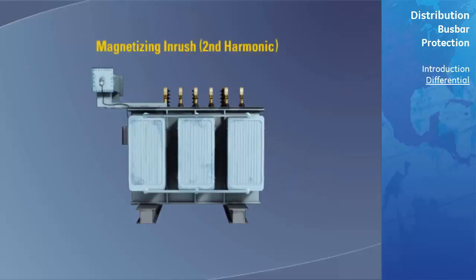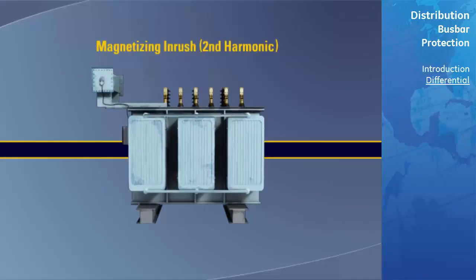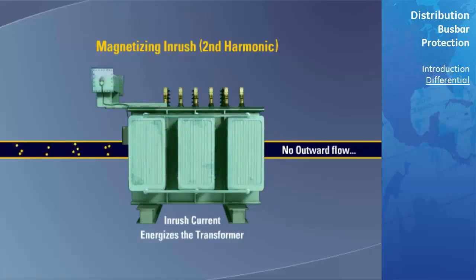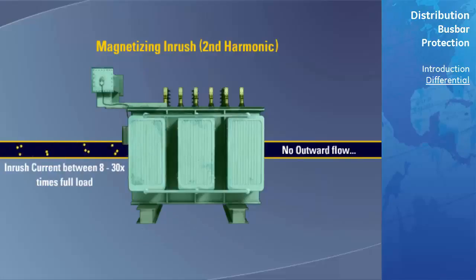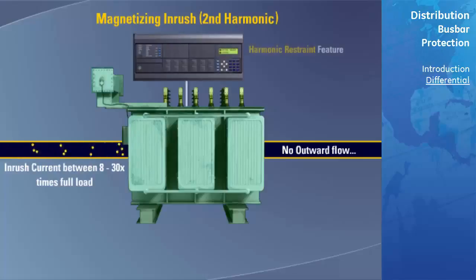Magnetizing inrush or second harmonic. This is a normal characteristic of a transformer that is being energized. When the system voltage is applied to a transformer at a time when the steady-state flux should be at a different level from that existing in the transformer, a current transient, known as inrush, occurs to build up the flux. Inrush currents between 8 to 30 times the full load current flows into the transformer with no current flow out. This current flow would normally appear as an internal transformer fault to the differential element. However, many years ago it was determined that there is a large second harmonic component of this inrush current. Modern microprocessor relays include a harmonic restraint feature to assure that the relay will never operate on inrush.